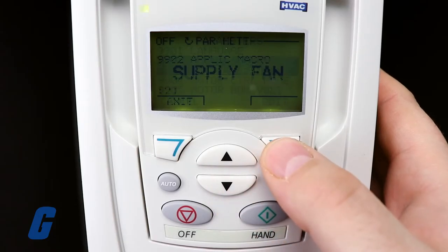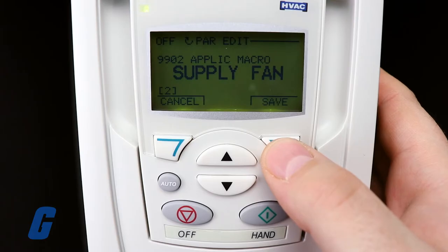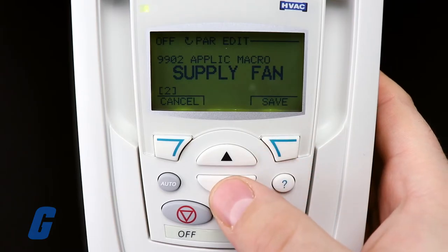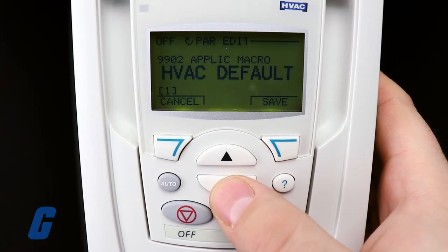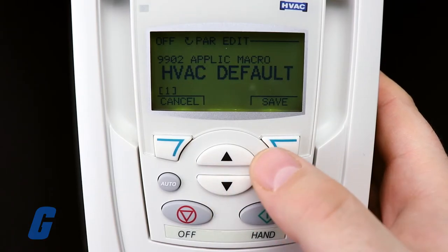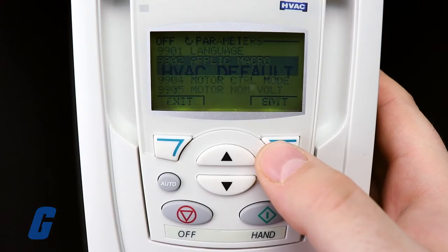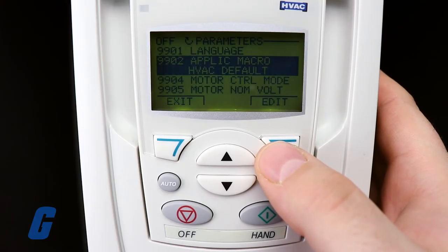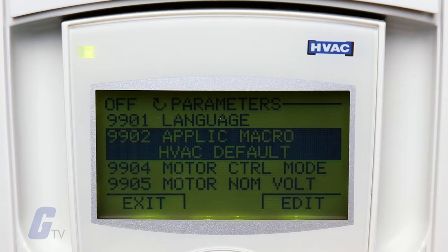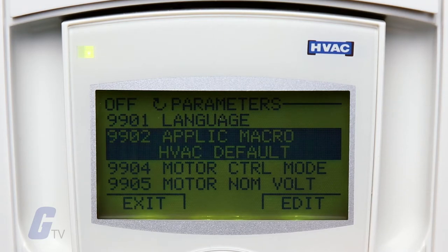From here, press the edit key to open the settings for this parameter and set it to option one. Confirm it with the save button and the drive will then reset to the initial factory default configuration, giving you a clean slate to configure the drive again.